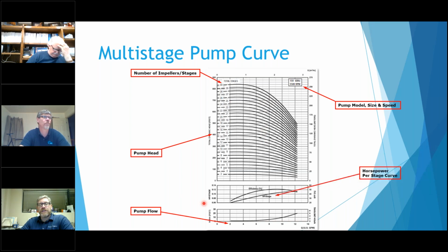And down here this is your horsepower curve. Now this is the horsepower per stage. So if you got a 10 stage, it's basically 10 times wherever you're trying to operate. So if you're trying to get to 8 GPM, you go up to this line. The horsepower reading is over here, so it hits right at 8. You come over, it's 0.10 horsepower per stage, so that roughly uses about 1 horsepower for that 10-stage pump.